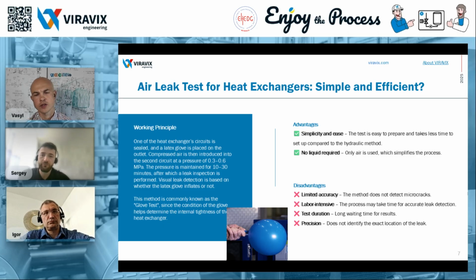Sergey, my first question for you. Could you tell us, what's the main advantage of this method compared to the hydraulic one? Because essentially, the only difference is the medium we use for testing the heat exchanger. So what makes the air method more convenient? Basically, you don't need any liquid for the test. Just hook up the air, and that's it. You pressurize the heat exchanger to the required level, and you're done. That's the simplicity of it, and the main difference from the hydraulic test.